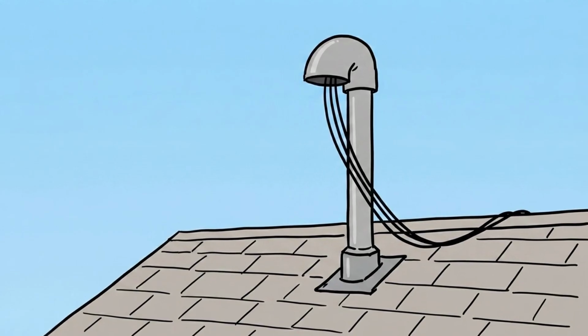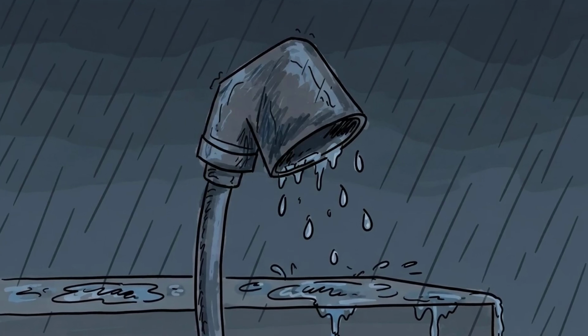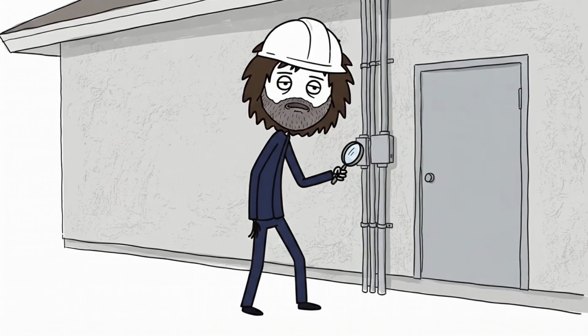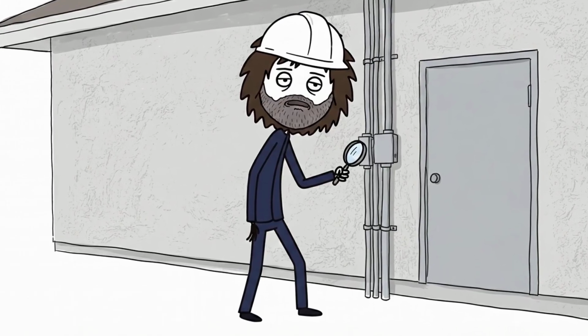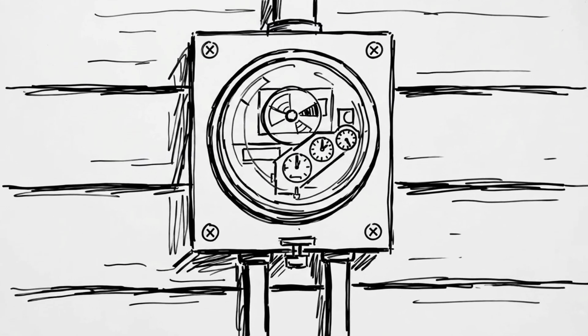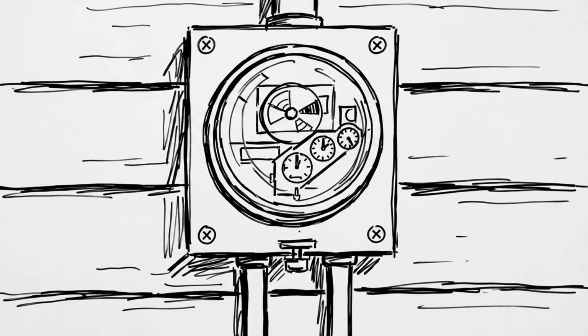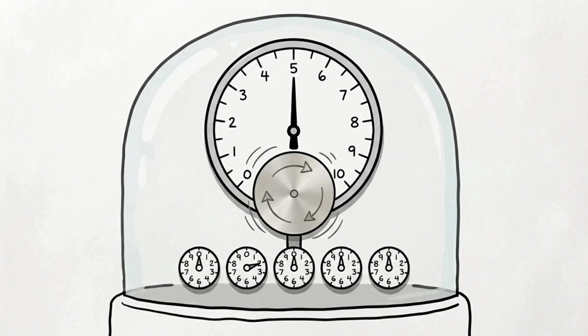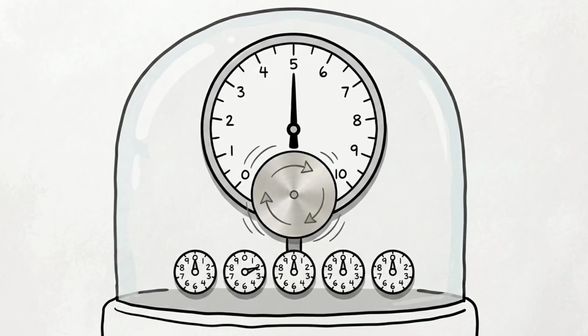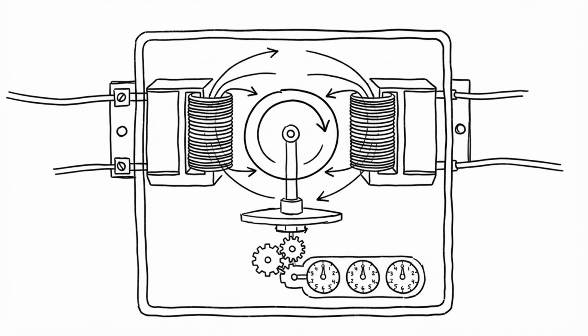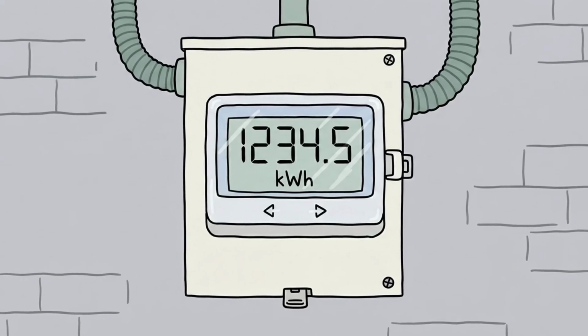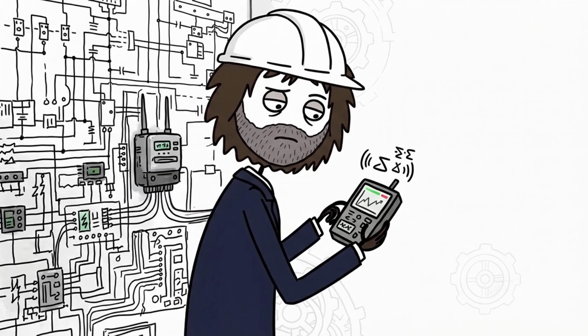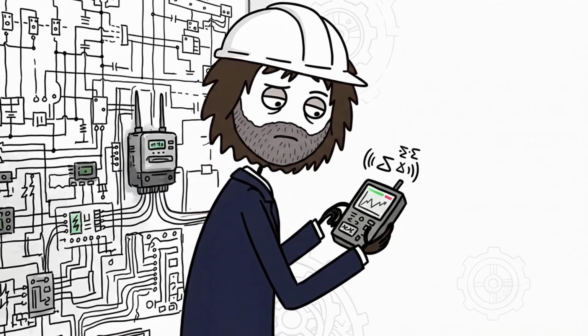From the pole transformer, 3 twisted wires, 2 insulated black hot conductors, and 1 bare aluminum neutral support cable make the final leap to your house in what electricians call the overhead service drop. The wires attach to a sturdy mast head on your roof called a weatherhead, which uses a downward curving hood to keep driving rain from entering the conduit pipe and travel downward along your exterior wall directly into the utility electric meter.